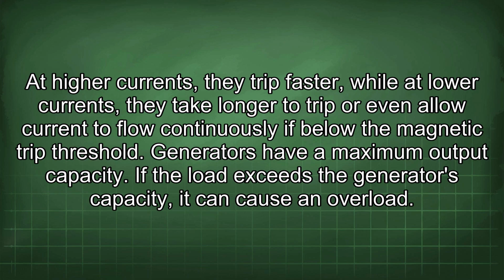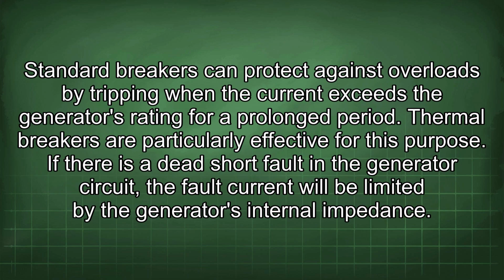Generators have a maximum output capacity. If the load exceeds the generator's capacity, it can cause an overload. Standard breakers can protect against overloads by tripping when the current exceeds the generator's rating for a prolonged period. Thermal breakers are particularly effective for this purpose.